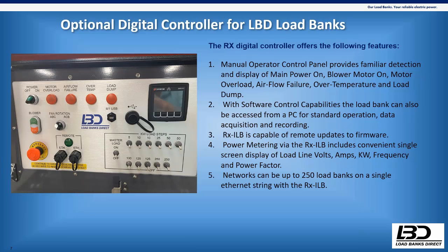One of the main differences I mentioned with the previous controller is that you automatically get 1 kW resolution because it's all based on binary steps. This style controller is not - it's got the standard 5 kW resolution, just like a manually controlled load bank. So that's one of the differences between the ECU and the RX controller. That 1 kW resolution has a lot of pros, but if you're never going to be using it with a little tiny generator, it's not always necessary - it might be a little overkill. We see the ones with 1 kW resolution used a lot in test cells and labs and stuff like that.